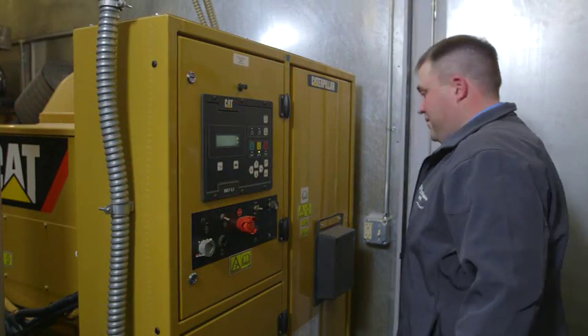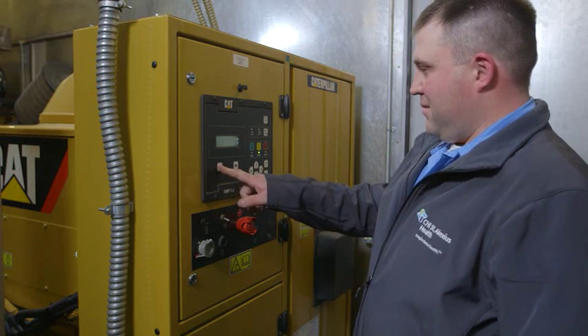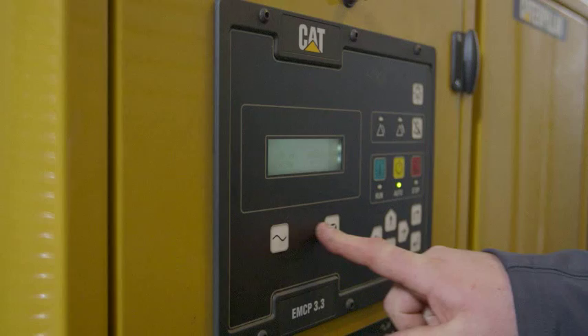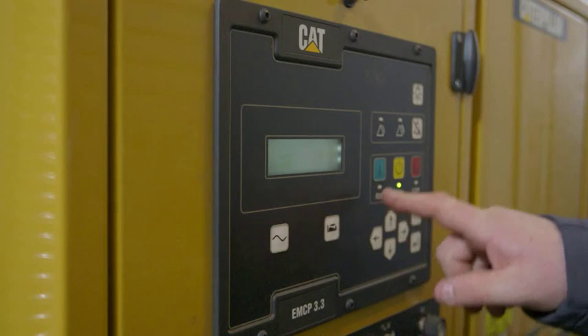The EMCP control is a computer system on the front end of all 6 of our generators. They help phase in to the system, and as they phase in, it closes breakers so we don't have bad currents going through our system. It's a pretty clean transition.